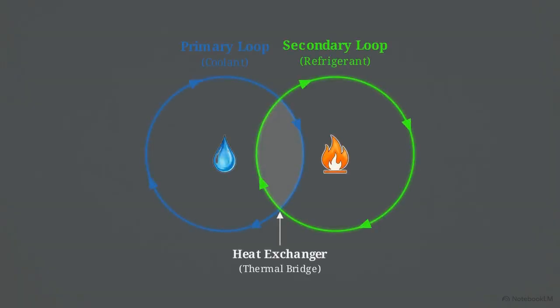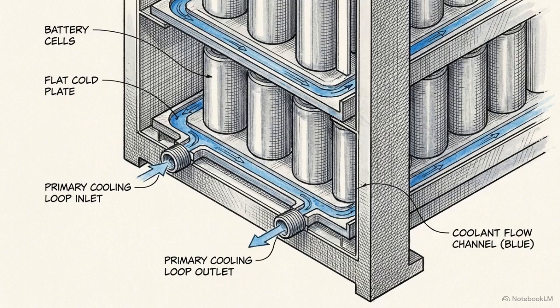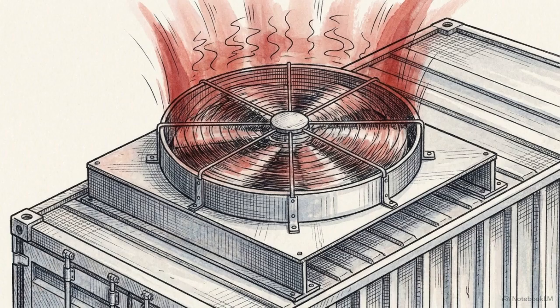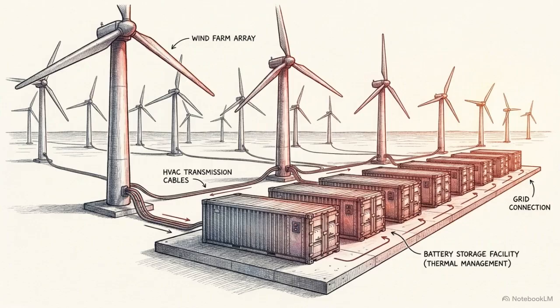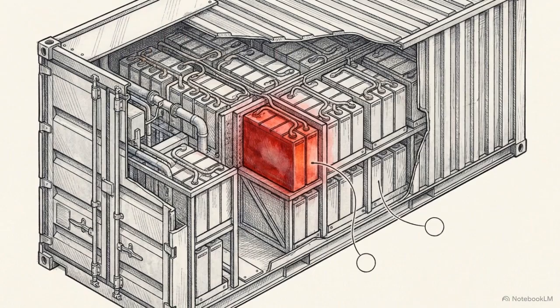The architecture relies on two distinct continuous flow paths. A primary fluid loop cycles internally to absorb heat directly from the battery cells, while a secondary refrigeration loop captures that heat and injects it into the outside atmosphere. Without aggressive, precisely controlled thermal management, massive energy storage systems degrade rapidly under load, becoming liabilities to the grid rather than assets. To design the primary loop, we have to look closely at the internal mechanics, isolating a single active battery module within the container.